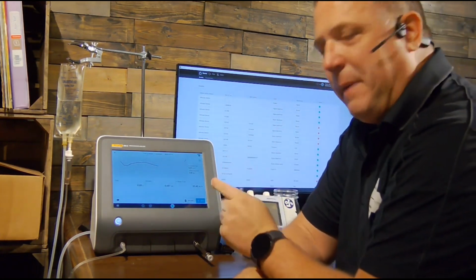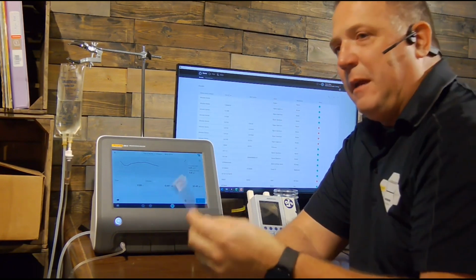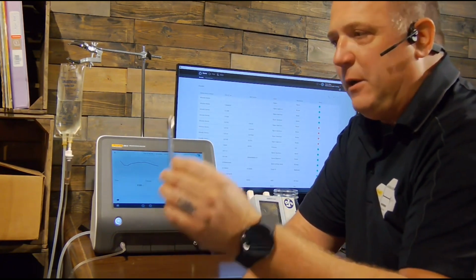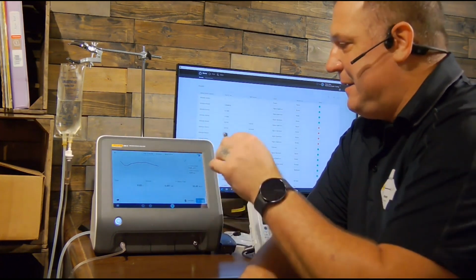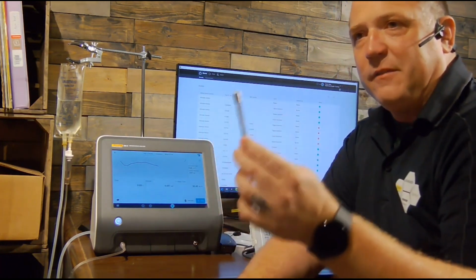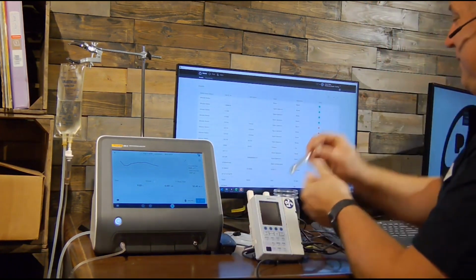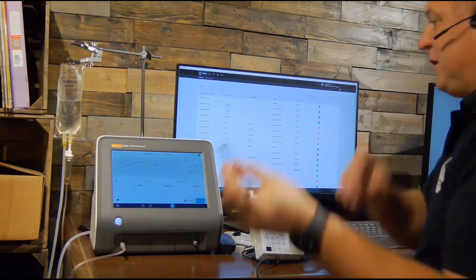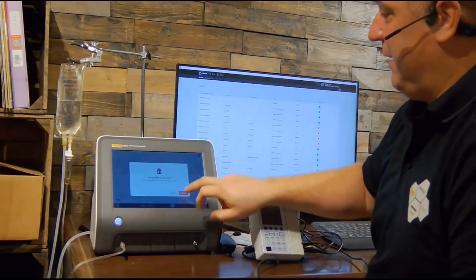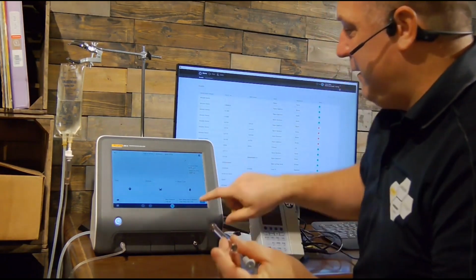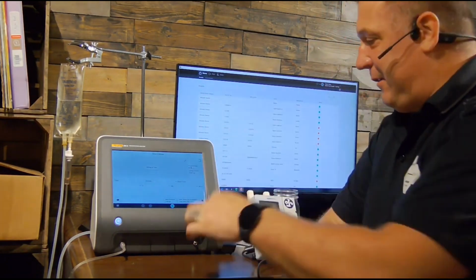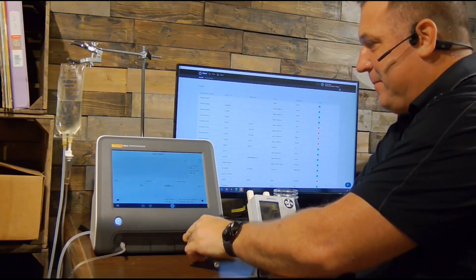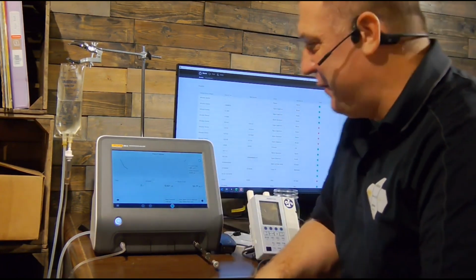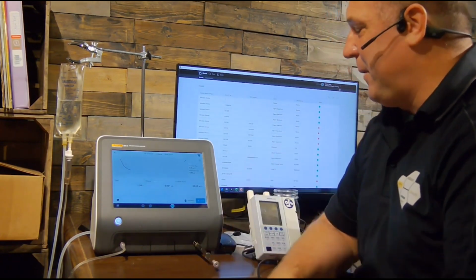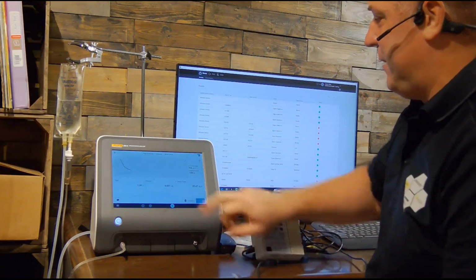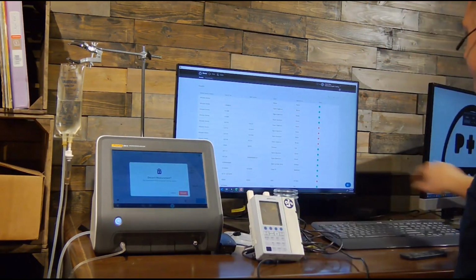The second thing I want to tell you is if I did this same thing with other analyzers, it'd take 10, 20, or even 100 of these syringes to get that test to start. And this started with less than 1. And actually, I'll show you something else that's kind of neat. I don't need to push this in. I'm just going to discard this test and start over again. If I start my test and then connect this, it's so sensitive that when I connect it in, it senses it as a flow. So it is very, very sensitive, super high resolution. All right, we'll discard this test and get rid of this syringe.